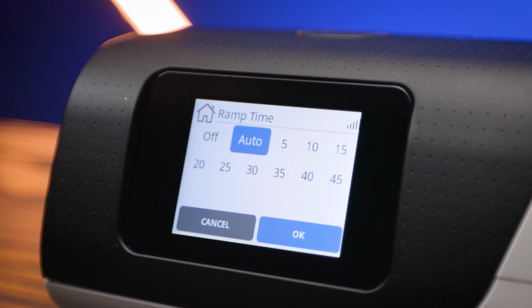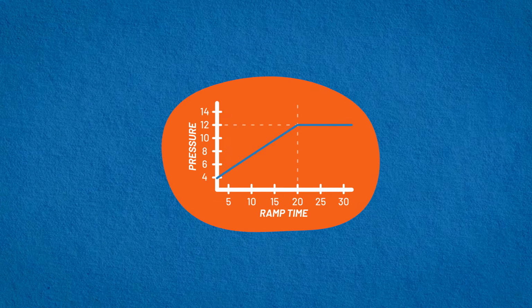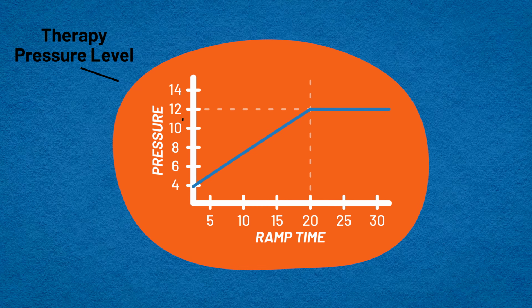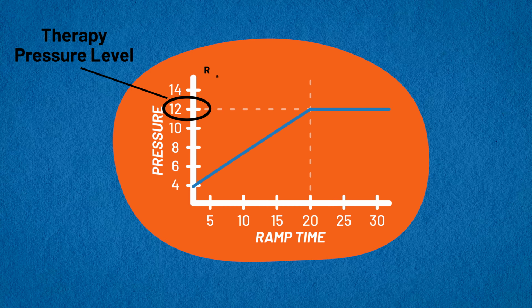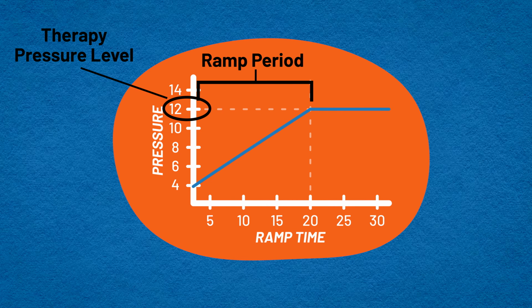Second, you need to set a ramp period. This is the time it takes for the machine to get to the therapy pressure levels. To complete the ramp analogy, the therapy pressure level is like the pressure level at the top of the ramp, and the ramp period is the length of that ramp.